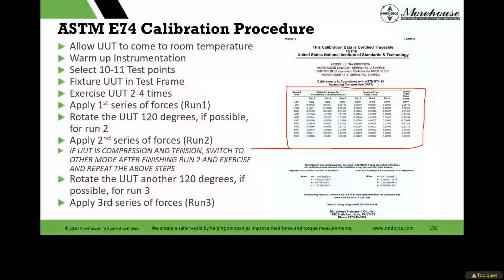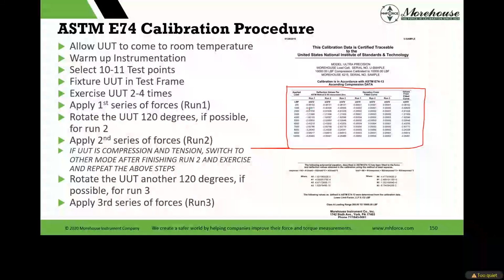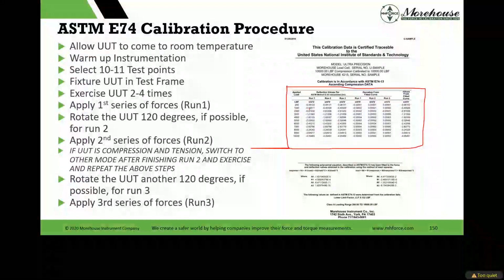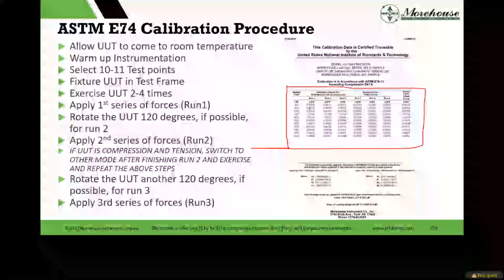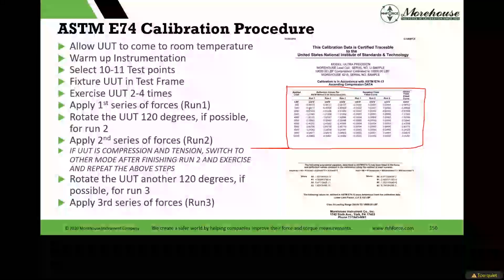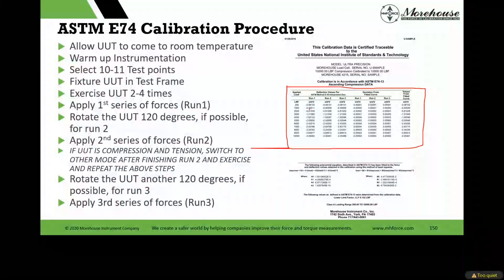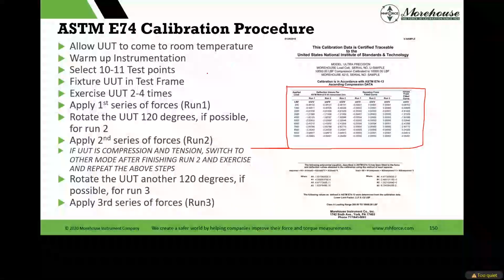So someone sends the equipment in, we allow it to come to room temperature. Usually a 24-hour soak is good. If somebody sends us in a 1,000,000-pound load cell that weighs 1,000 pounds, 24 hours is probably not enough to come to room temperature. If somebody sends us in something that weighs 1 pound, 24 hours is probably overkill. So there is that effect on materials. Though a good rule of thumb is about at least the day before.